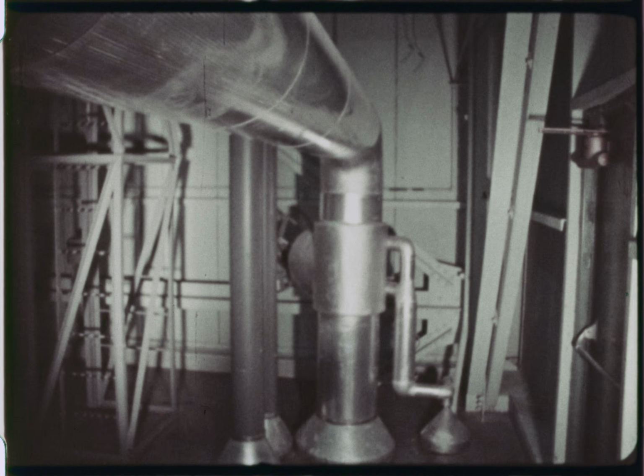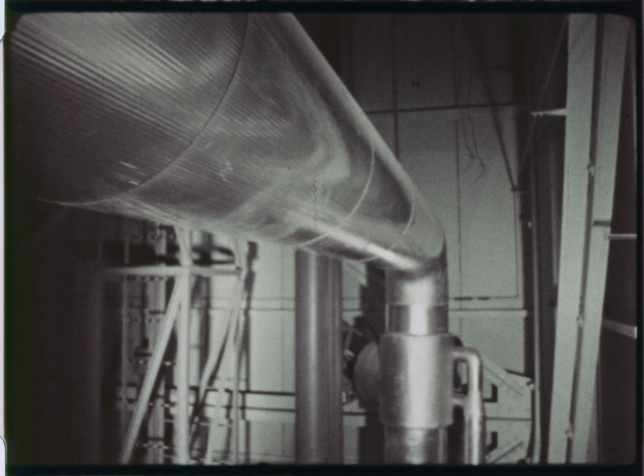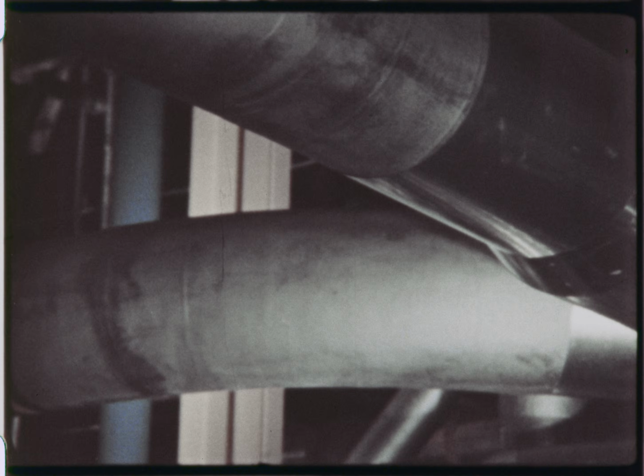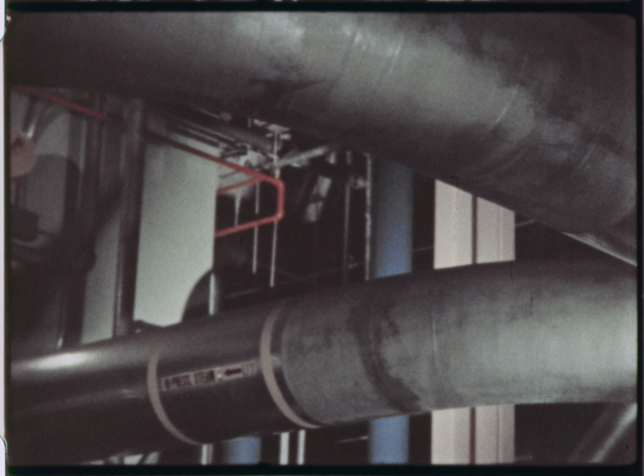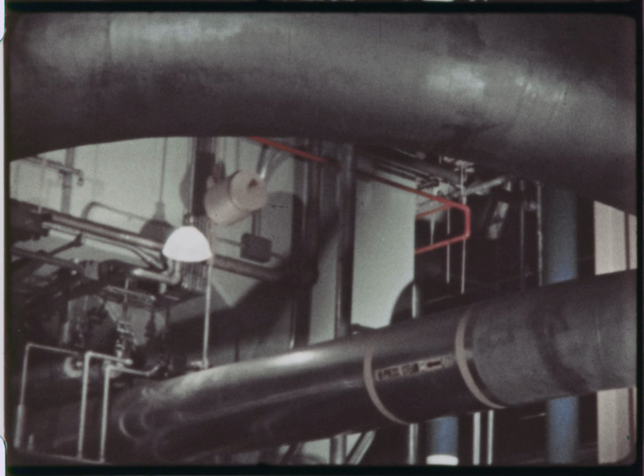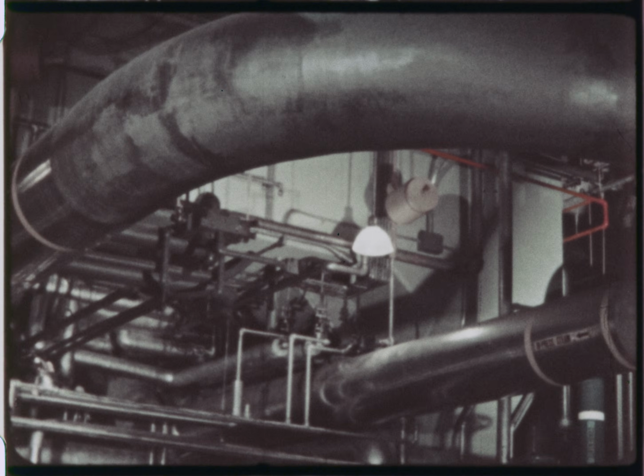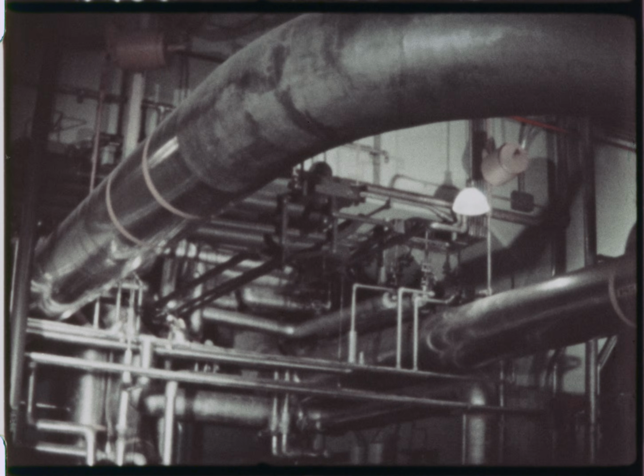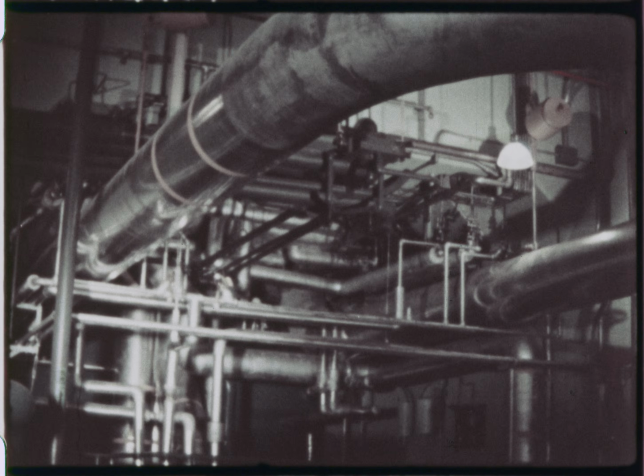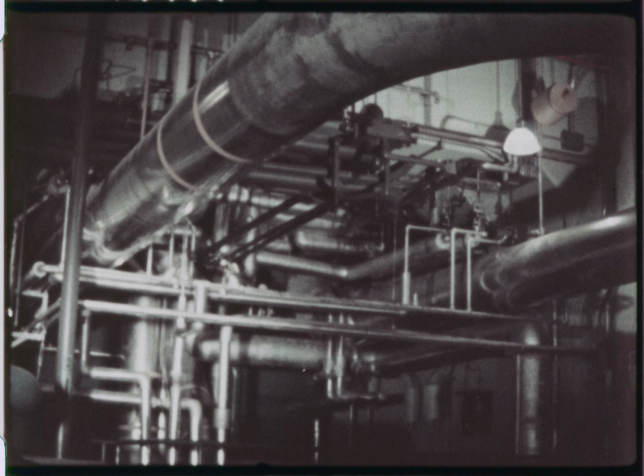Steam piping connects each of the 3 steam generators to the main steam line, and the 825 degree Fahrenheit, 800 pounds per square inch steam is fed to the turbine generator. After the steam passes through the turbine, it is condensed to water and returned to the individual steam generators at 325 degrees Fahrenheit. High-grade superheated steam is produced by the liquid sodium heated generators.